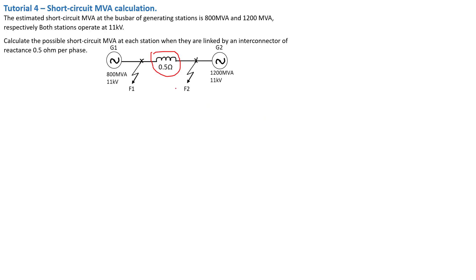What is a reactor? Usually on large systems — 800 MVA and 1200 MVA are quite huge generators — these systems that are interconnected to other systems require additional impedance in the form of reactors, to limit the short circuit value to safe levels. That is the role of the reactor in the system.